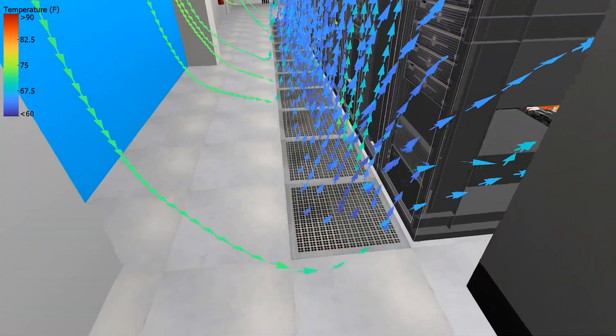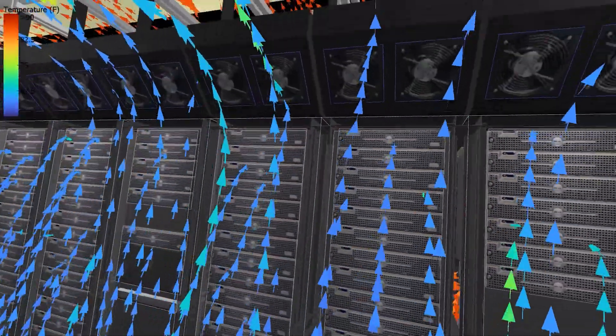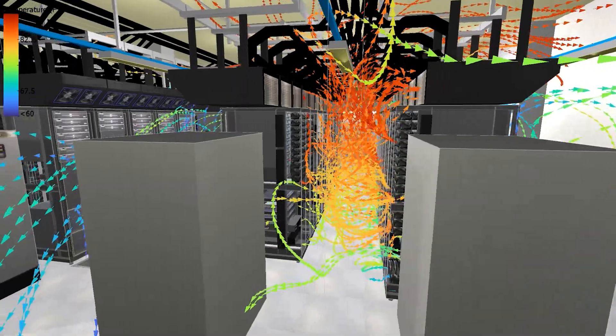We can identify opportunities to improve and affect design modifications. We get design-specific engineering data such as ASHRAE compliance, SLA compliance, effect of leakages, pressure distribution, and percentage cooling capacity utilized from the CFD results using Cadence data center design software.